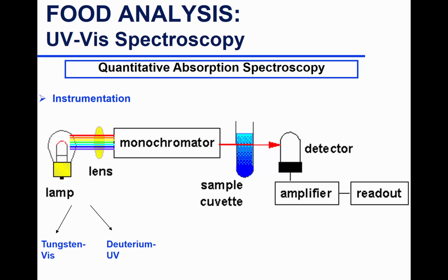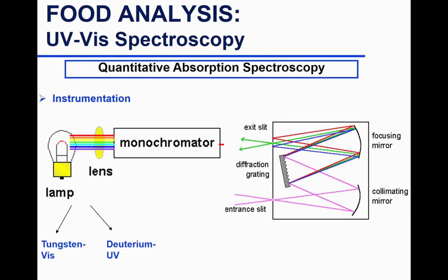And what happens is you have the light projected into a monochromator. And we talked about monochromator before, is when your light gets diffracted using a grating system, and then the light is broken down into multiple wavelengths, and then the slit that is there allows the exit of a particular wavelength. So this can be moved for different experiments to allow absorption at different wavelengths.